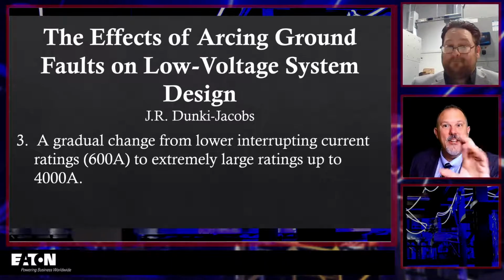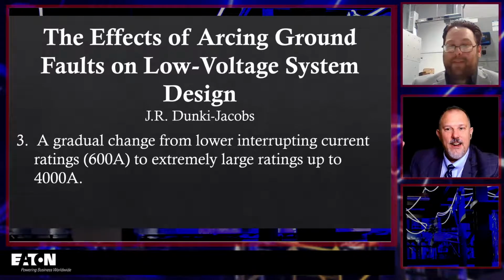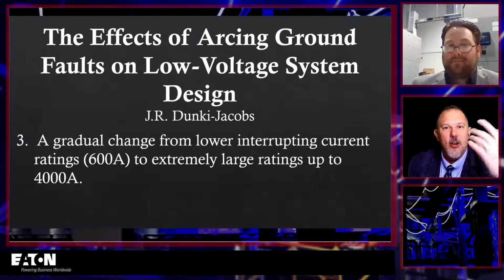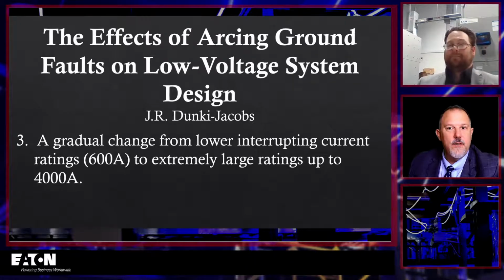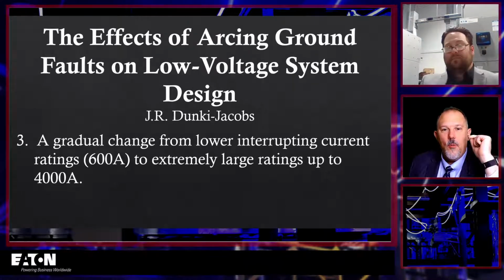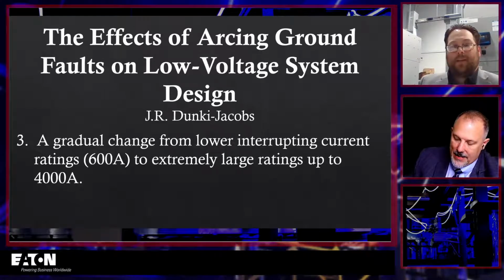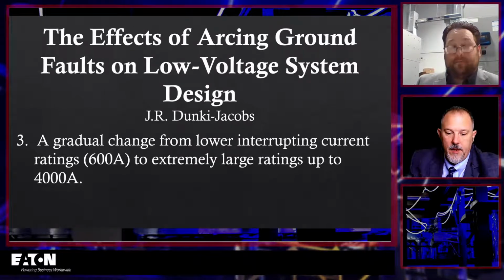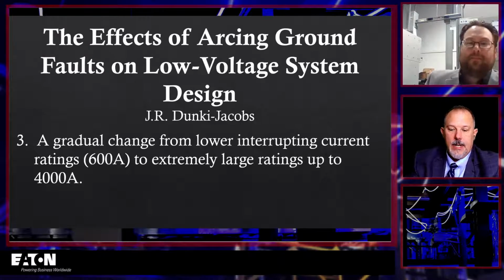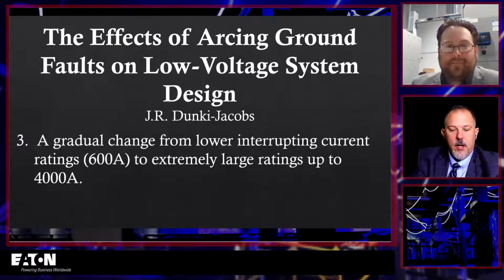Yeah. Right? Because you've got a 4,000 amp breaker, you've got a higher voltage than before, your fault currents are going to be lower because it's a higher voltage. You're into the long time region, you push the instantaneous way over to the right. And then what we were experiencing in the industry, I'm going to go back to the substantiation from NEMA when this went in. It said, however, high impedance faults such as arcing to ground are more prevalent than bolted fault currents. In grounded electrical distribution systems, these faults may start phase to phase or phase to ground, because that's what happens, right? And then Dunki-Jacobs showed that it goes three phase.